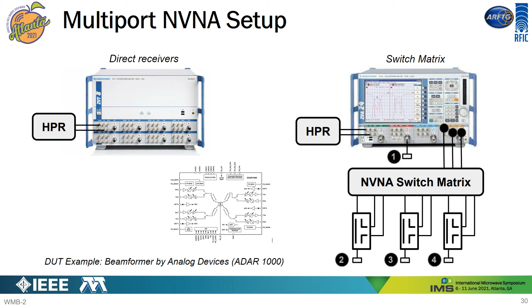Let's start with the 1-port relative calibration of a VNA or NVNA. For this purpose, we measure 3 perfectly known gamma standards: gamma short, open, and load, and 3 uncalibrated measurements for those standards: gamma M for short, open, and load. From those 3 measurements, we can solve the linear system, leading us to the 3 error terms related to the measurement port number i. An absolute calibration means we have 4 error terms, but with a short open load, we have performed a 1-port relative calibration, leading us to only 3 error terms: beta prime, gamma prime, and delta prime. This calibration is incomplete. If we consider alpha is equal to 1 for this calibrated port, we will say that the system is partially calibrated.